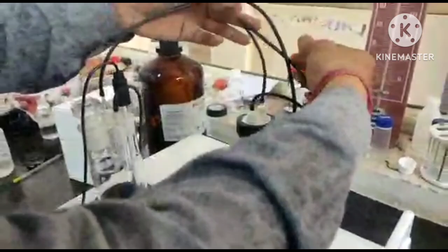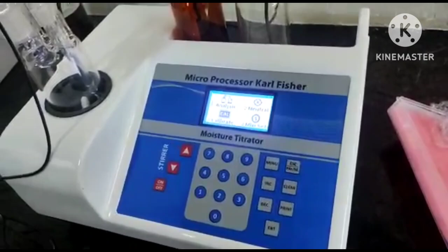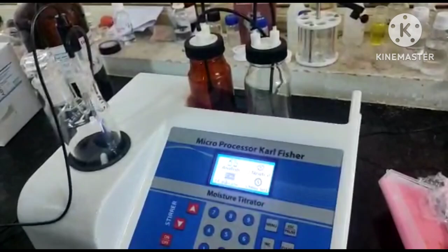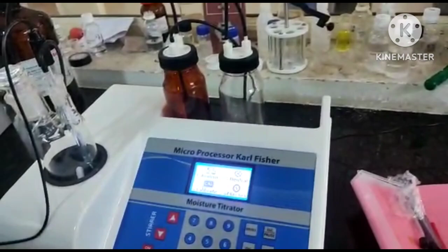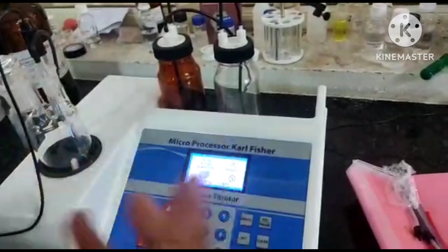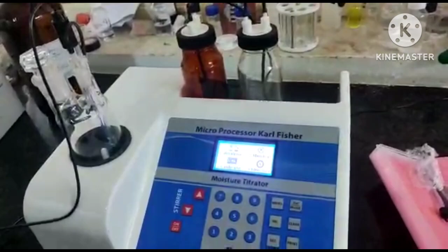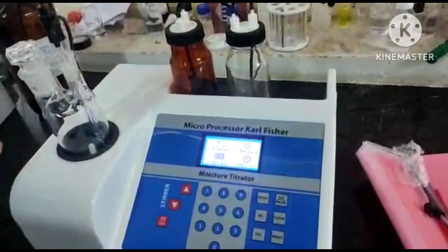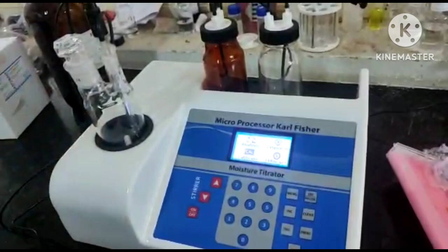Thereafter we have to connect our power adapter with the machine. And now, as you can see, our machine is ready to use. So these are the primary connections that we have to make. In this we have to fill the amount of Karl Fischer reagent that is usable. So don't put more than your usable amount, because it has some limited time period, and we have to consume that amount of Karl Fischer reagent within that time period. So you have to put as much as you can consume of the Karl Fischer reagent. Then second, I have told that in this we have to put silica gel crystals. In the titration vessel, we have to put 35 to 40 ml of methanol, the dried methanol. So these are the primary connections that we have to make.